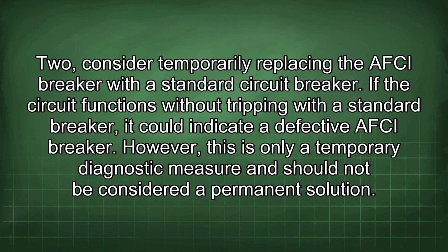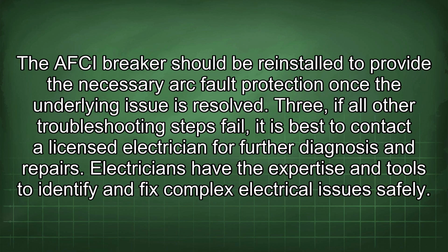2. Consider temporarily replacing the AFCI breaker with a standard circuit breaker. If the circuit functions without tripping with a standard breaker, it could indicate a defective AFCI breaker. However, this is only a temporary diagnostic measure and should not be considered a permanent solution. The AFCI breaker should be reinstalled to provide the necessary arc fault protection once the underlying issue is resolved.